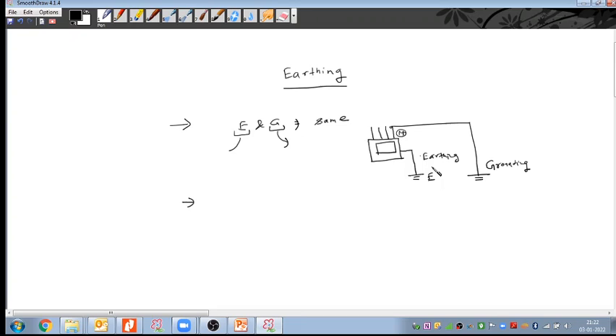And earthing, in my perception, is connecting solidly to earth, keeping the resistance as minimum as possible. In most cases it is less than 1 ohm. We try to target minimum resistance, less than 1 ohm, or as low as possible. Your perception is correct. Your understanding is correct. That is perfect.